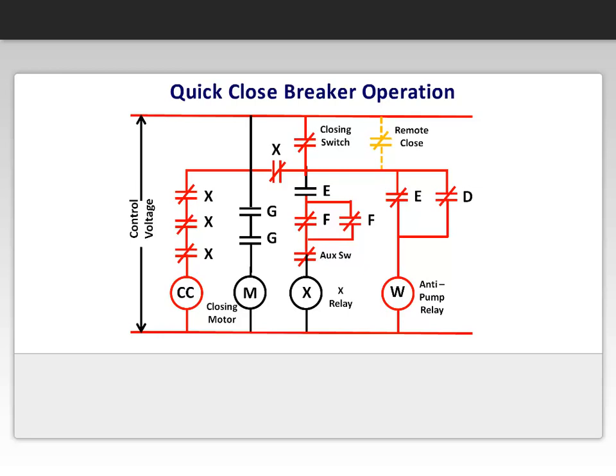When the breaker closes, the mechanically operated G switch is closed to energize the motor again, and the F switch is open and de-energizes the control relay. The auxiliary switch contacts open, preventing the control relay X from energizing until the breaker is tripped open. With the G contacts closed, the motor charges the closing springs, ready for the next closing operation.